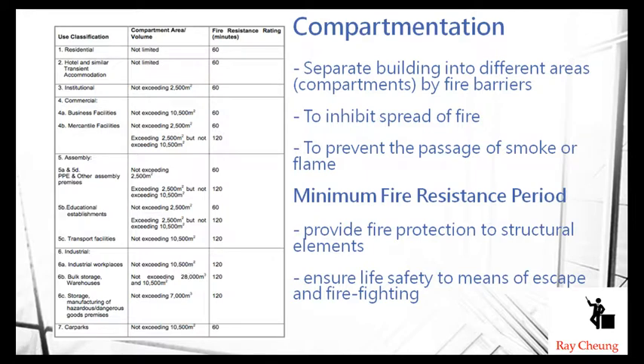If you want the area to be larger than this, you need to provide fire barriers to separate between the two areas. The fire-resistant rating of those barriers should be two hours.